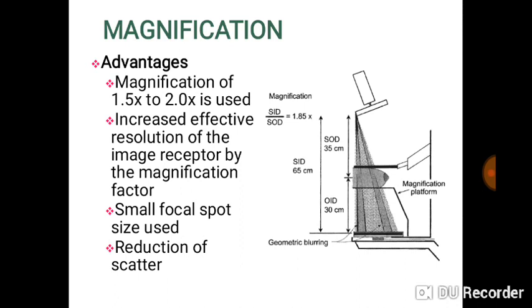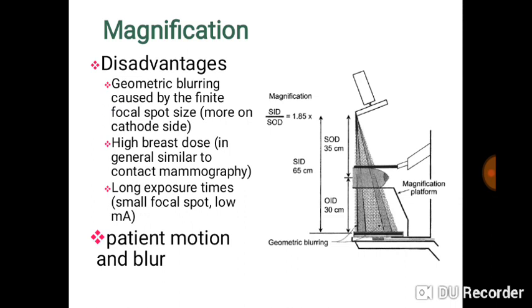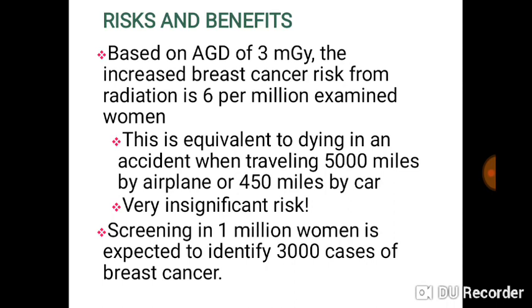Magnification can also be employed in mammography when you are trying to get a certain portion of the breast enlarged so the radiologist can see more of a particular area. Once there is a palpable mass, a nodule, or a calcification seen on ultrasound or other modalities and you want to confirm it on mammogram, you can palpate the area involved and apply 1.5 or 2 times magnification so the image will be larger and clearer. There are some disadvantages to magnification: geometric blurring, high dose of radiation, and long exposure time.